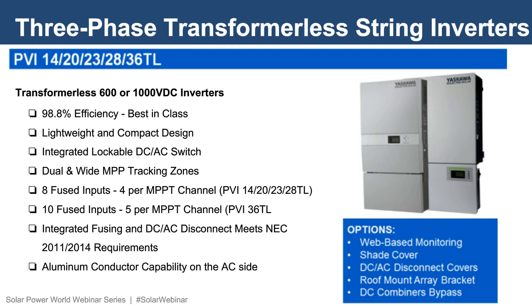Other features I'd like to highlight on these products are that we can accept aluminum conductors for the AC connections. This allows long industrial feeders the ability to use low-cost materials and still meet voltage drop requirements with large conductor sizes. Finally, Solectria can offer a variety of options with these products, including shade covers if installed on hot, harsh environment rooftops, web-based monitoring services, array brackets, and DC combiner box bypass kits, which will be utilized later when I talk about our RSD-COM, or our Rapid Shutdown combiner products.